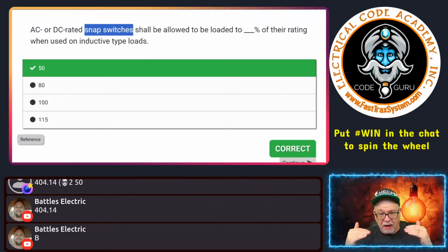We're like, okay, stop. And then immediately we start looking for anything that has a reference to the question. 50%, 100%, 80%, 100% at 115. And we saw the 50% and we saw that it was dealing with inductive type loads. So if you have an AC or DC snap switch and you're going to be using it on inductive type loads, then guess what? The AC or DC snap switch is allowed to be loaded to a certain percentage of its rating. So again, if dealing with inductive type loads, then it can only be loaded up to 50% of whatever that AC or DC rated snap switch is.